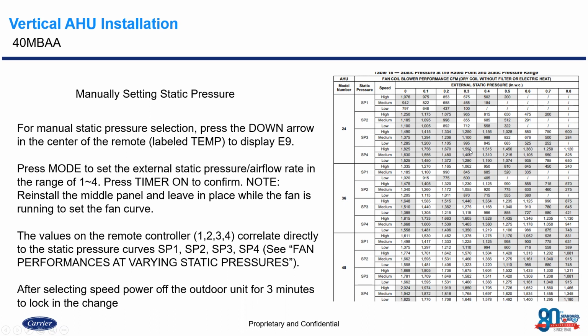Now, of course, not everybody takes into consideration measuring the static pressure and figuring out the CFM. Usually, if you need a decent amount of CFM, I typically go between SP3 and SP4, SP4 being the max that we can push that unit to. Okay. So what you're going to do on your wireless controller is, you see that E9, you go ahead and press the mode button. You're going to see a 1 come up. You then want to use your temperature up and down arrows to navigate to 1, 2, 3, or 4, which we know by looking at this chart is SP1, SP2, etc.